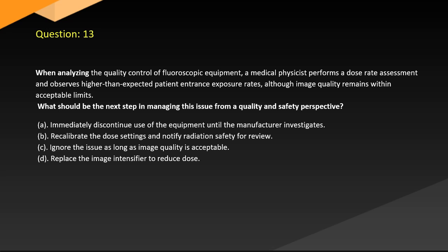A. Immediately discontinue use of the equipment until the manufacturer investigates. B. Recalibrate the dose settings and notify radiation safety for review. C. Ignore the issue as long as image quality is acceptable. D. Replace the image intensifier to reduce dose.